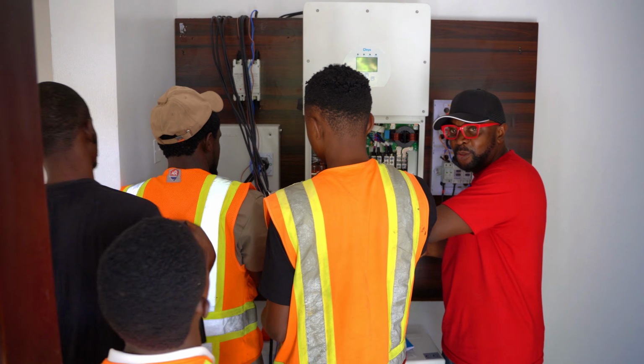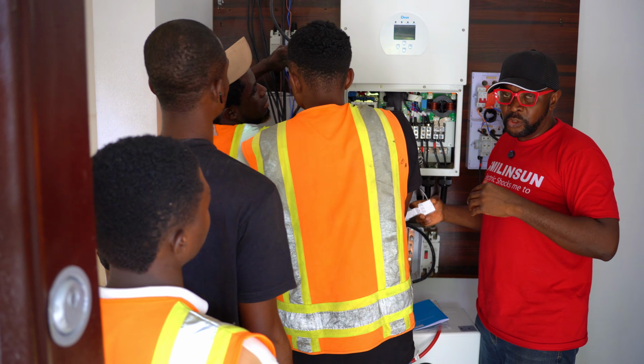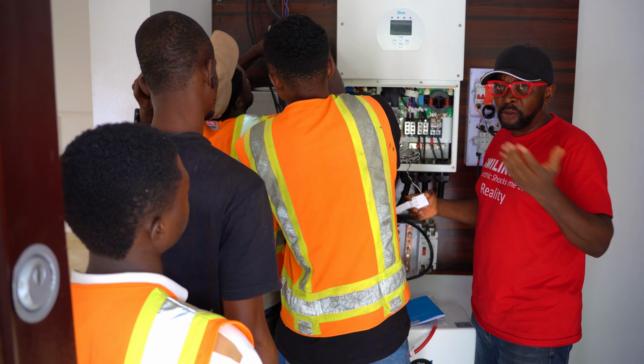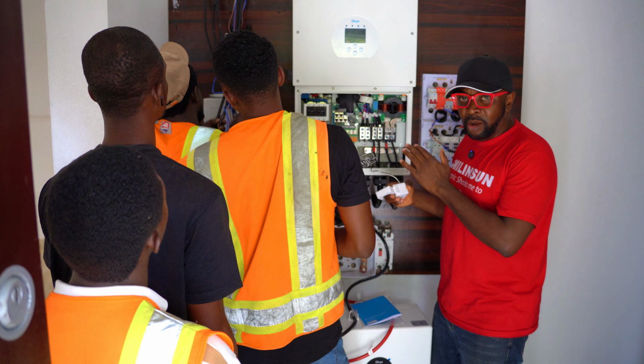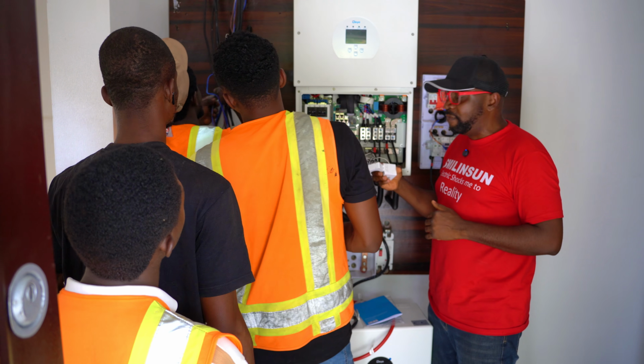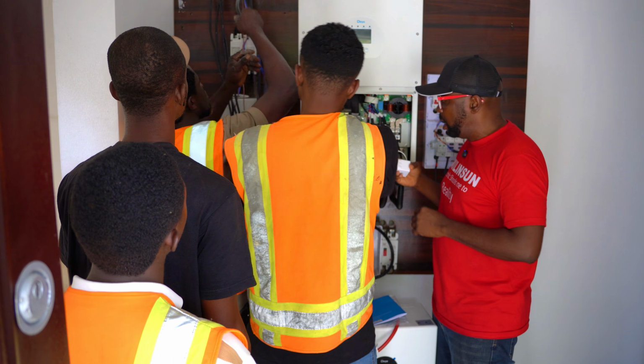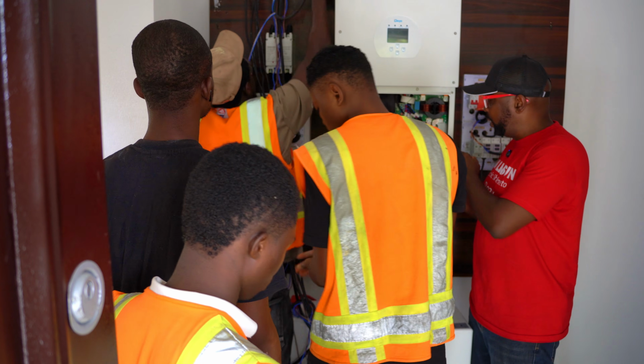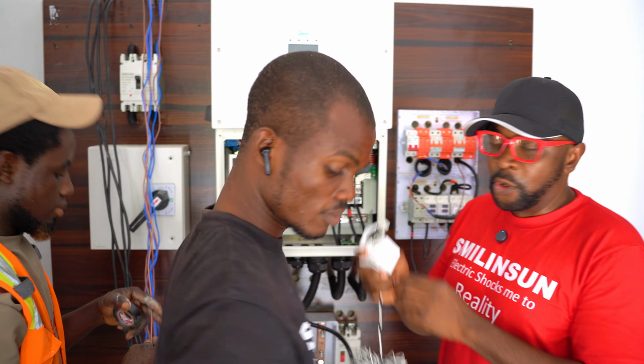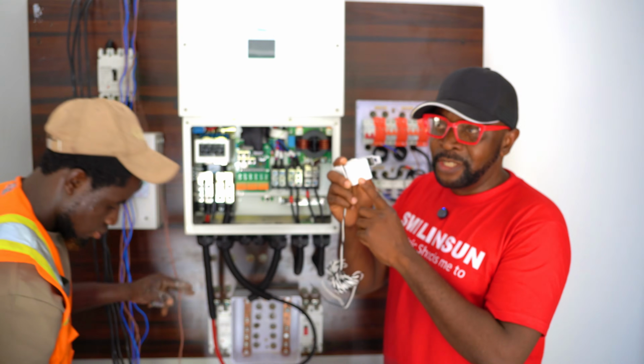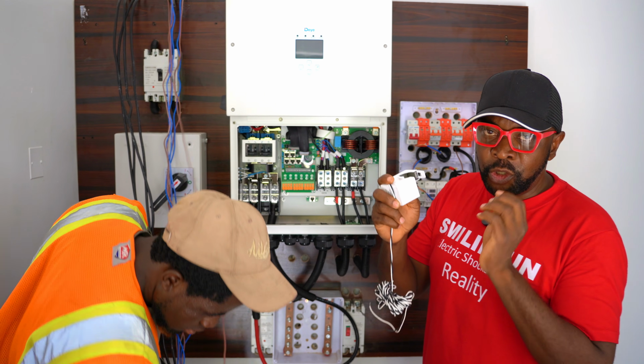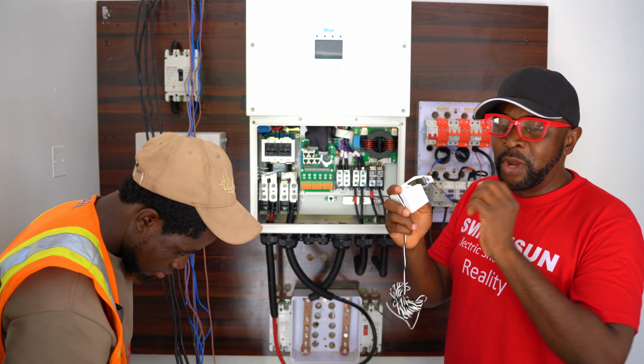We're connecting the cables right now from the PV, while also constructing the carport to take the remaining 23 panels. Right now we're connecting the PV and also connecting the current transformer sensor here. It's meant to be connected on the live wire that comes from the grid. This arrow sign, you need to pay attention to it, because it ensures that you connect it properly the way it's meant to be connected.